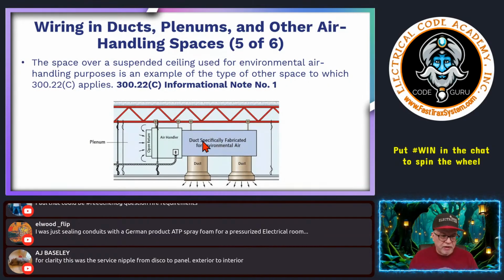So in order to penetrate this, I have those lists of wiring methods that allow me to penetrate this assembly. But up here, since this is used as an environmental airspace, because it's sucking air into the unit and it's not individually ducted down into each room, I'm able to use different wiring methods like standard MC, but you still can't use non-metallic products up here. That's what they mean by environmental airspace in the use of 300.22.